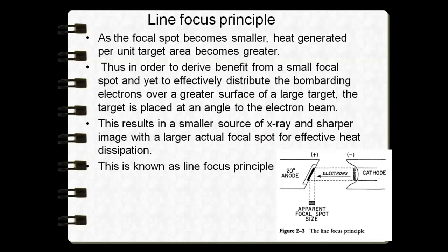To achieve a smaller focal spot with heat spread over a wide area, the anode or target is angulated at a 15 to 20 degree inclination. With this angulation, the electrons bombarding the target produce an apparent focal spot size of around 1×1 mm. At 90 degrees, where electrons hit perpendicularly, the focal spot size is larger — around 1 to 3 mm. This is why we use the line focus principle to attain a smaller focal spot for a sharper image.